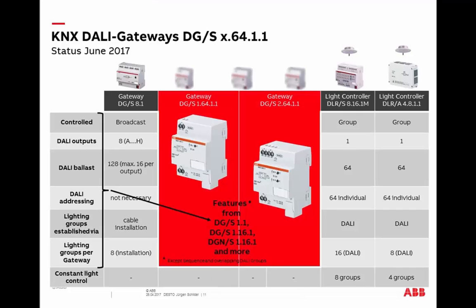We will replace these three devices — DGS 1-1, DGS 1-16-1, and DGN/S 1.16.1 with emergency lighting — by two new components: DGS 1-64-1-1 with one DALI output, and DGS 2-64-1-1 with two independent channels. In principle, very similar devices and functions — the second device simply has two channels. We cover all functions from the existing three devices and have more features. One small note: the sequence function and overlapping DALI groups, which existed in the DGS 1-16-1, are not available in the new devices. However, as you will see with the new light grouping options, this is not a real disadvantage.